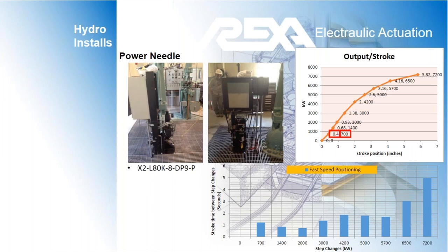If the set point needs to change, say for pond control or frequency recovery, the actuator can do so for a 100% duty cycle on demand. The graph on the top right of this slide shows the different set points for a given output. Notice the different increments of movement between each step change. Some of the step changes are as small as 1/4 of an inch to about 2 inches to regulate water flow.